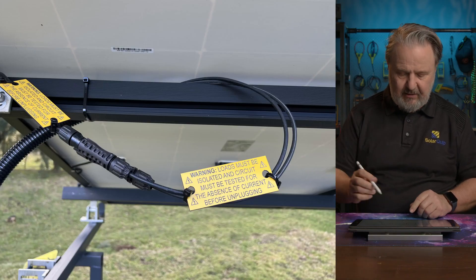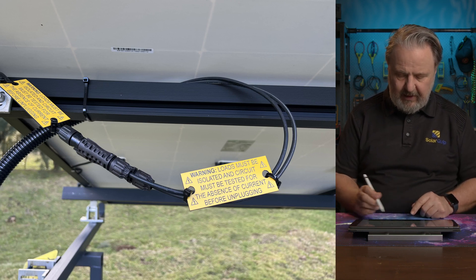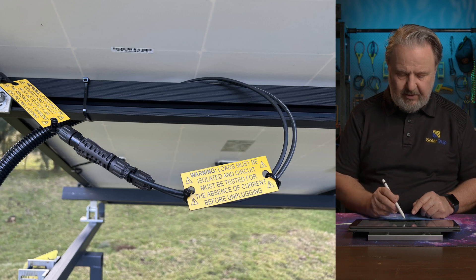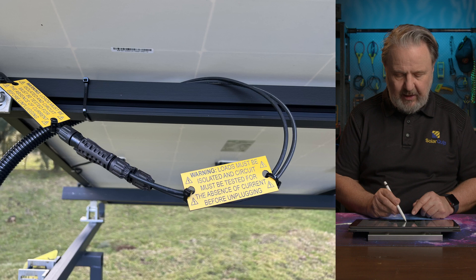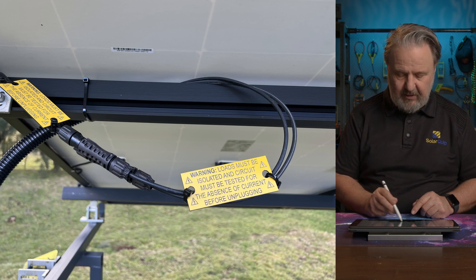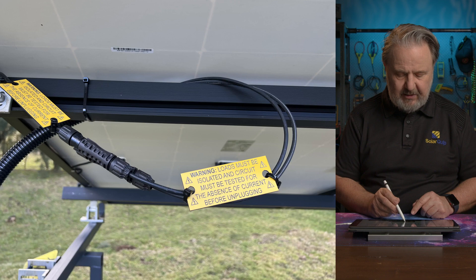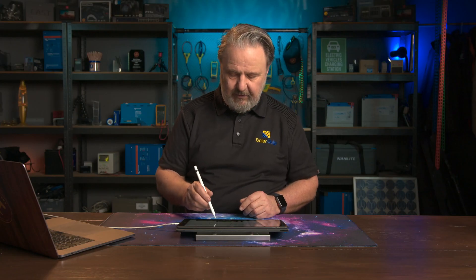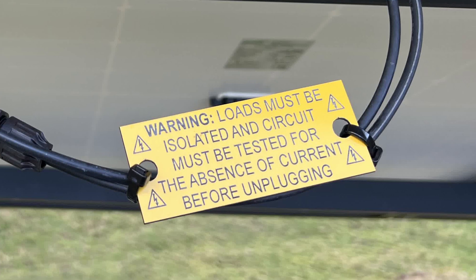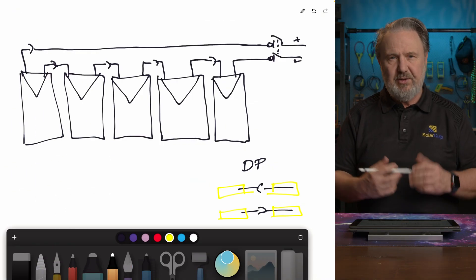So unplugging one of those disconnection points under load is very risky, and it's required to be labeled. The disconnection point must have a label stating 'do not operate under load' — a yellow label with black writing on either side of the cables — indicating that you should turn off the load first. This is usually licensed electrical work in every state and territory in Australia, and you should use the appropriate tool to disconnect it.